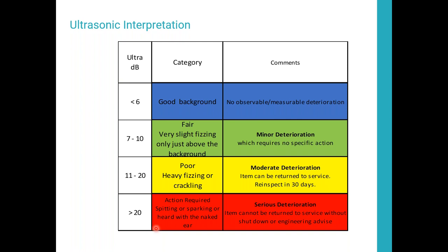Now, that may mean moving cables apart. It may mean putting a tape wrap and building an electrical stress cone, like you used to do with the old cable terminations, around that area and reduce the electrical stress in there that's causing the PD. It may mean a replacement of an insulator based on how damaged that insulator is. But it does mean if it's increasing, it's getting closer to failure point, so it needs more immediate attention.